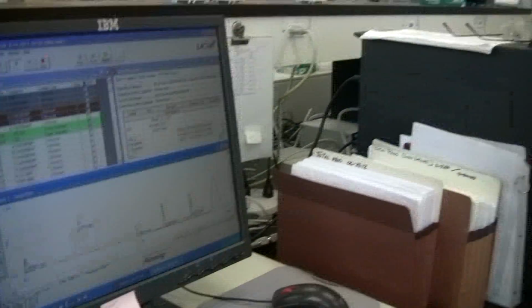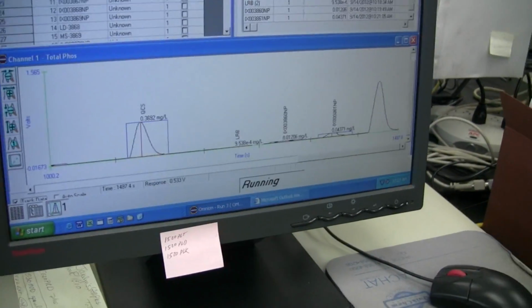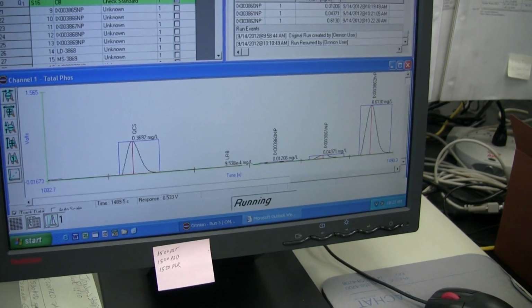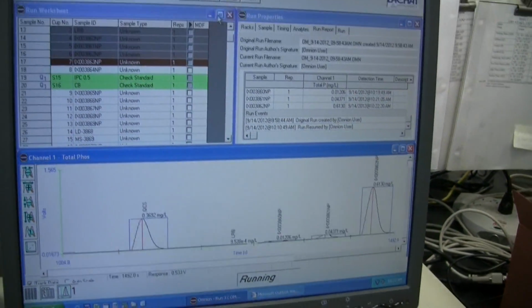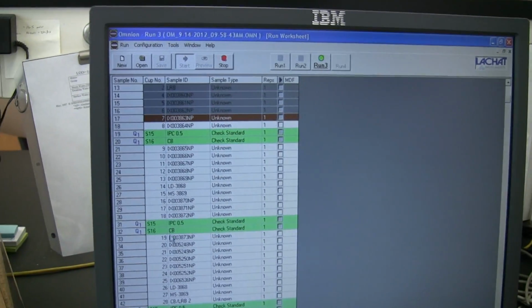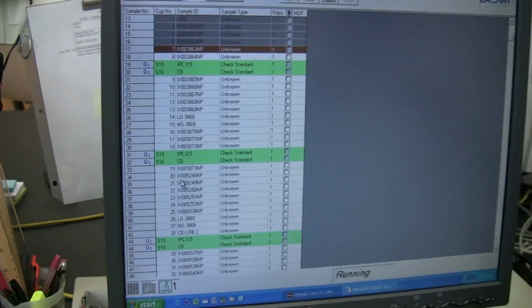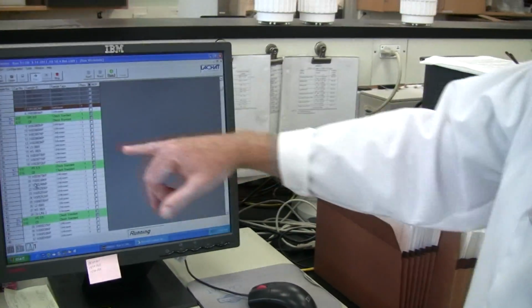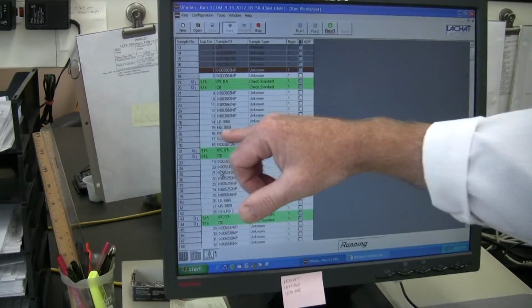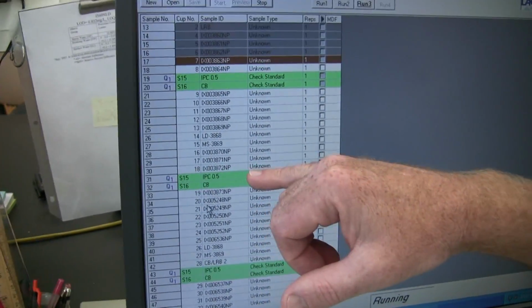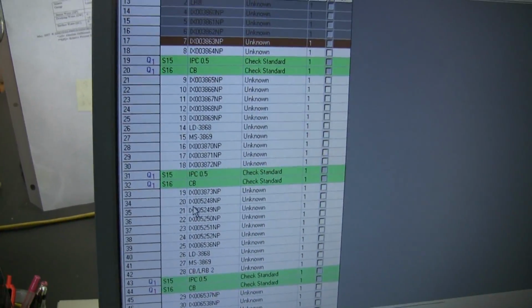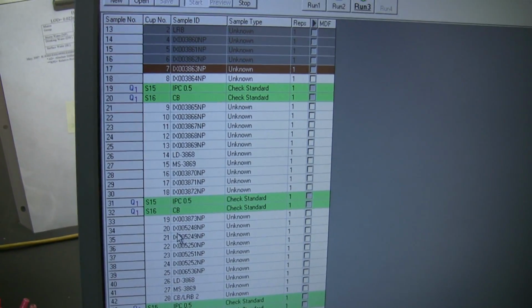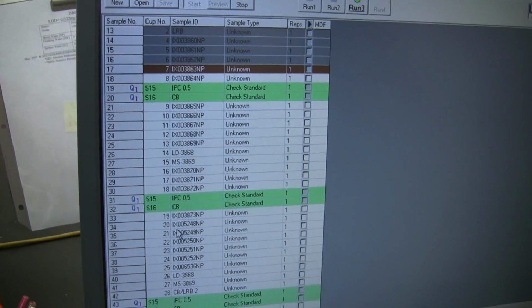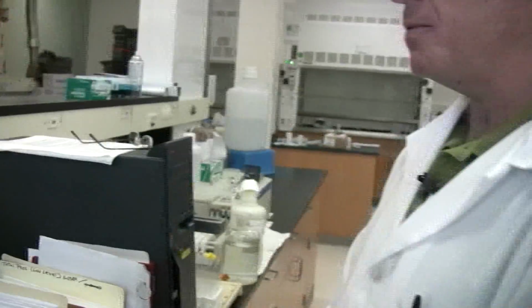And if it makes it through these next couple checks, I'll be happy. The green ones, if I look at, this is what we call our tray table. So it's basically the template that the sampler is running by. Each one of these numbers is a position number, and every 10 it's going to go back and do this check standard and check blank. And as long as those check standards and check blanks keep coming back within their quality control limits, the instrument keeps running. I'm happy. It's spitting out numbers, and we get our day's work done.